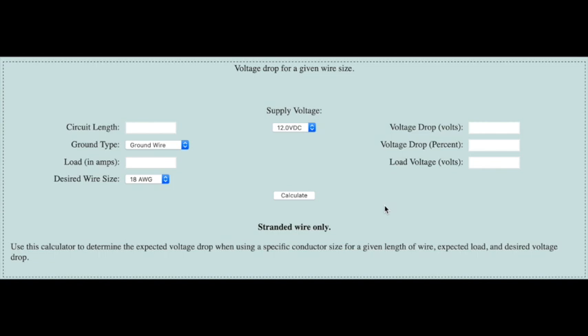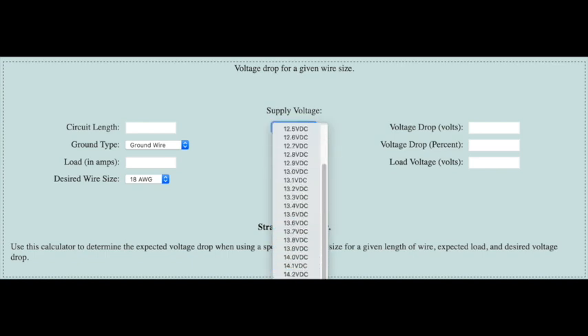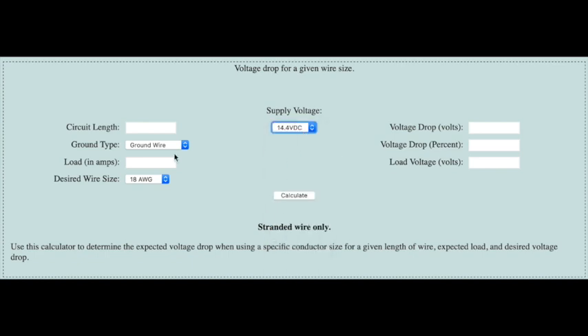This will tell you how much voltage you will lose over a given wire size and length of wire, depending on how much current goes through the wire. So we're going to go with a supply voltage of 14.4 volts. And we want a circuit length of 10 feet. And if we solve this for a 100 watt solar panel, we're looking at, let's say, 5 amps.